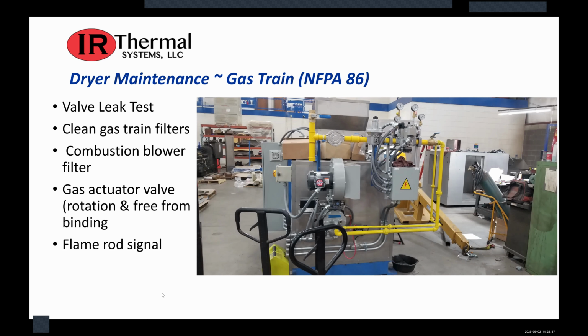Because there are specific regulations with gas trains that should be checked every year, to make sure that the double block and bleed valves aren't leaking over time, that you're not going to slowly flood your dryer with natural gas over a weekend, or to ensure that your purge time isn't getting changed over time due to a replacement of the purge timers or adjustments made during off hours.